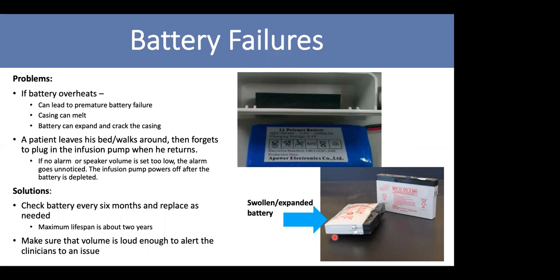So every 6 months when you check, the first year maybe you can still use it, the following year you need to replace it actually. And make sure the volume is set loud enough on your infusion or syringe pump, because sometimes you intend to set a low volume, so you don't hear the battery low signal, all that alarm. You cannot hear the alarm, so you end up not knowing what happened to the unit, and suddenly it shuts down. So make sure you always set the volume of the syringe or infusion pump loud enough to alert the clinical user.